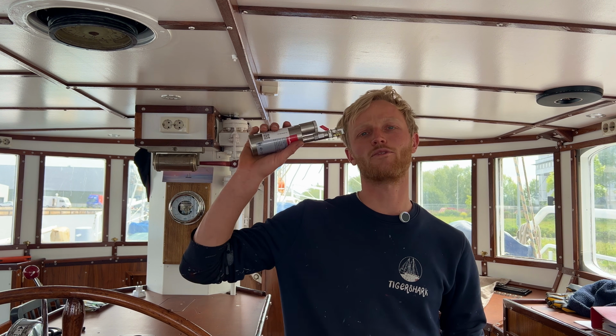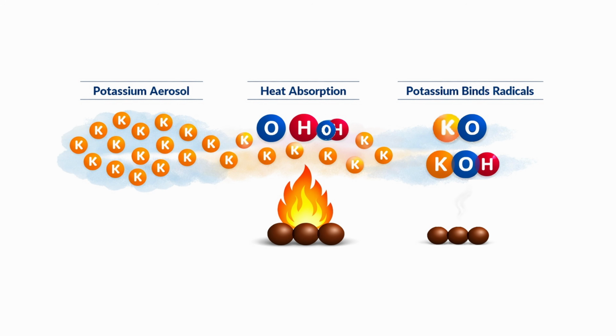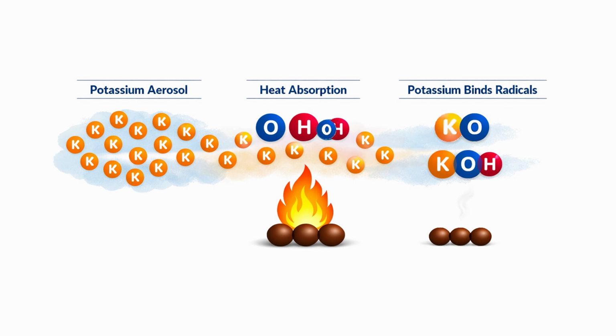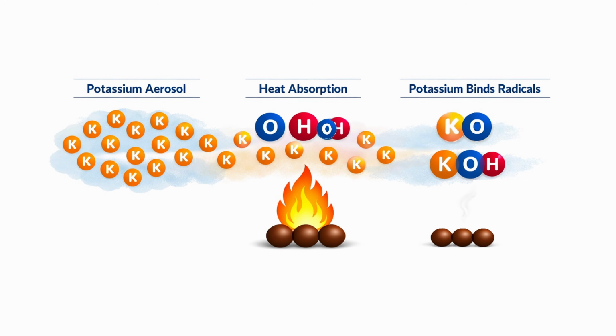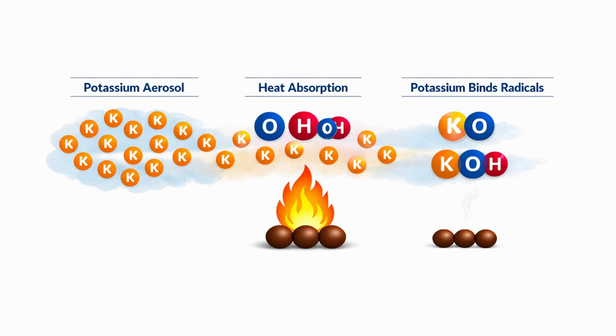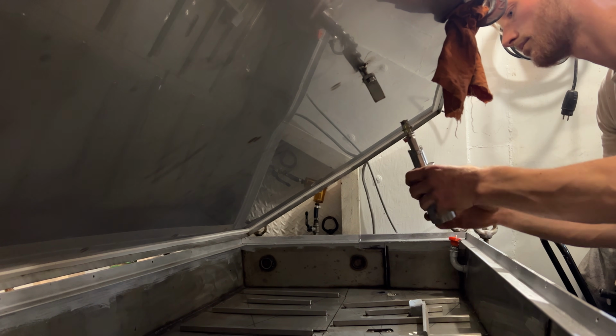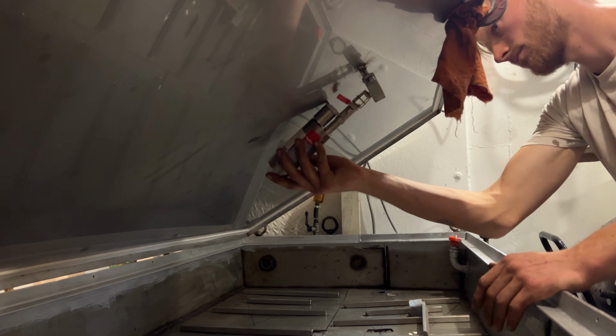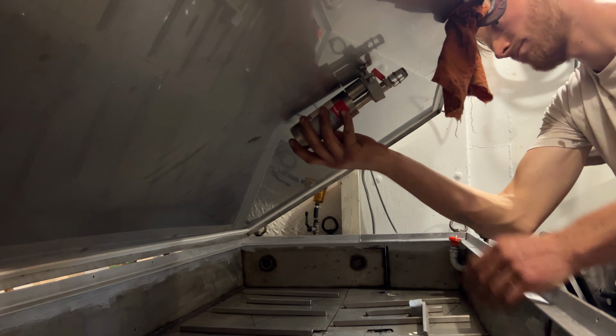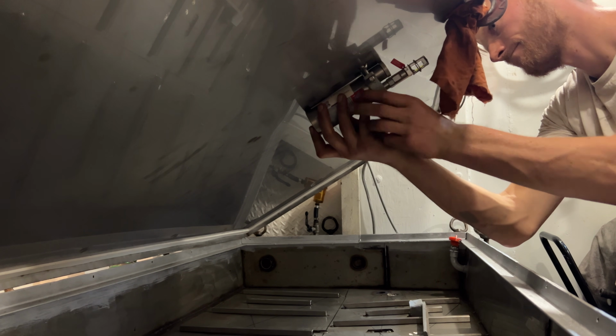And this is already where our first fire containment system activates. We're installing a FirePro aerosol canister that triggers at 79 degrees Celsius. And it fills the entire battery box with a potassium-based aerosol. That aerosol absorbs heat and it disables the reactive oxygen and hydrogen particles that are needed to sustain a flame. With a bit of luck, this already stops the spread of heat to the next cell, and it lets the one affected cell burn itself out in a controlled way.